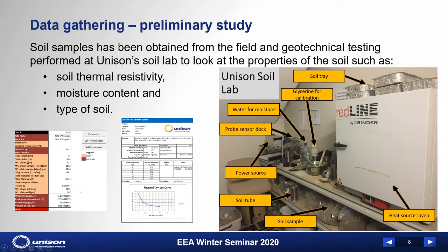Essentially, what we have at the bottom is a soil sample gathered from the field. That soil goes into a tube where it's heated up to provide a thermal dryout curve, which tells engineers the likely in situ conditions for a particular site and provides a range of the likely thermal resistivity the soil will experience.